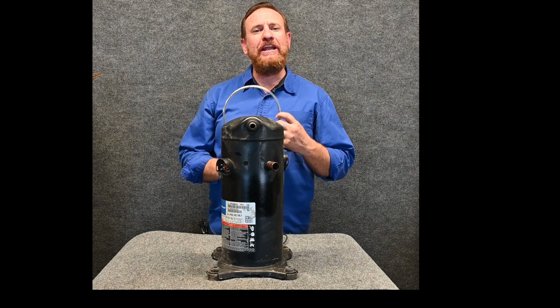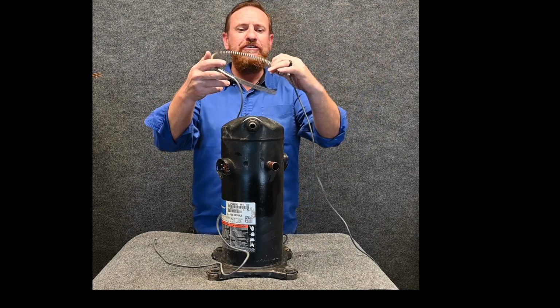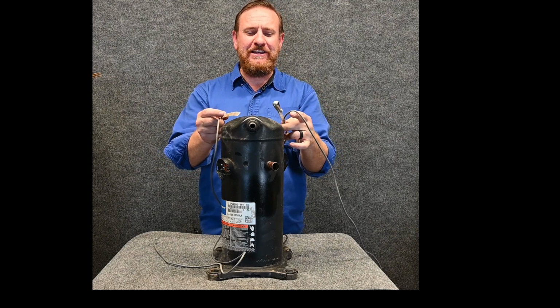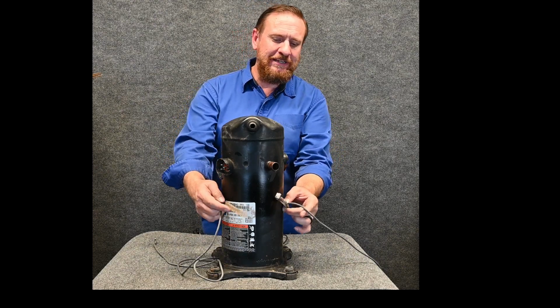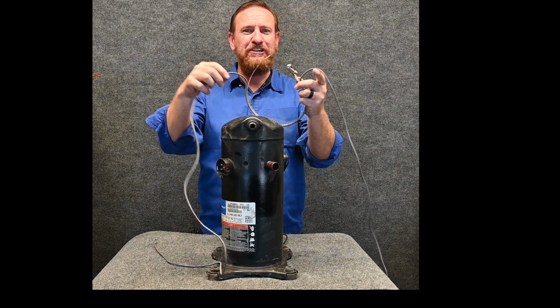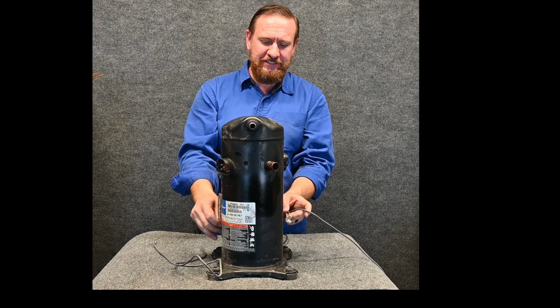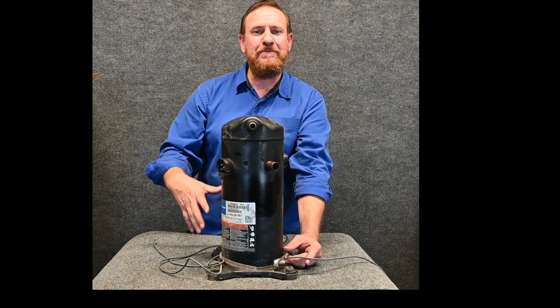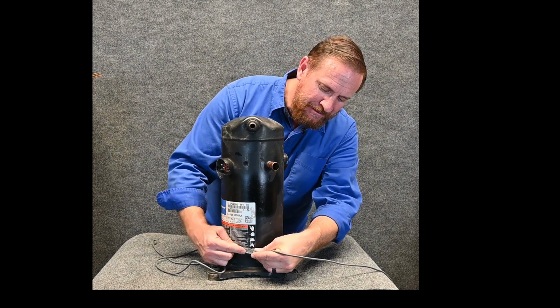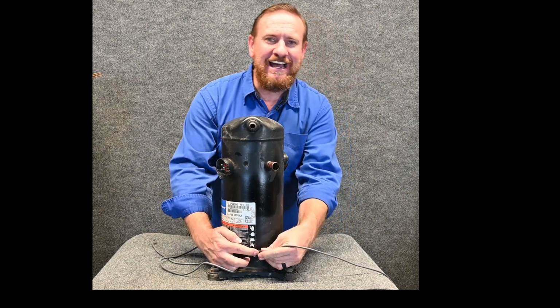And what we use is what we call a crankcase heater. So this is an external crankcase heater, and I call these belly bands. I don't know the proper name of it, but it's cool because they look kind of like a really giant hose clamp with the wires on it. And we put this at the bottom, the crankshaft in the very bottom, and this was the crankcase. Well, this is a scroll, so it didn't quite have that, but we could put this around and then tighten this up.